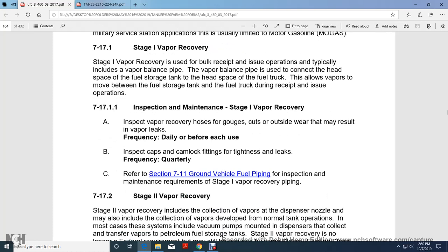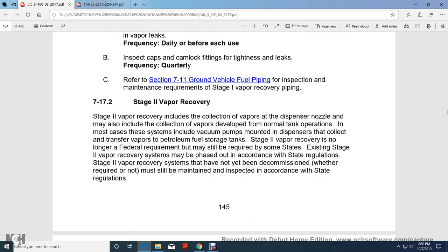Vapor recovery. Inspect vapor recovery hoses, gouges, cuts, and outside wear for the result of vapor leaks daily or before each use. Inspect caps of cam lock fittings for tightness and leaks quarterly. Refer to Section 7-11 Ground Vehicle Fuel Piping inspection maintenance requirements. Stage 1 recovery piping.